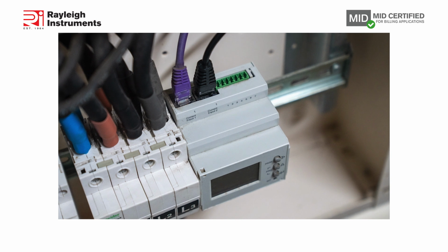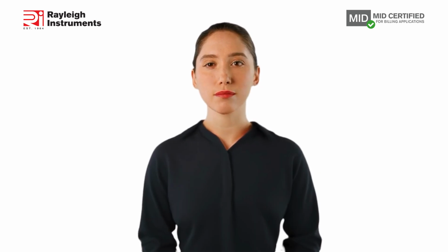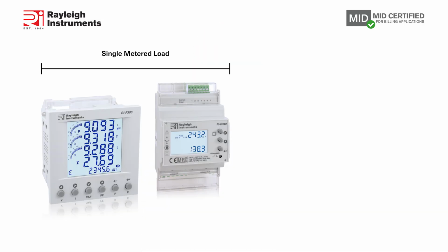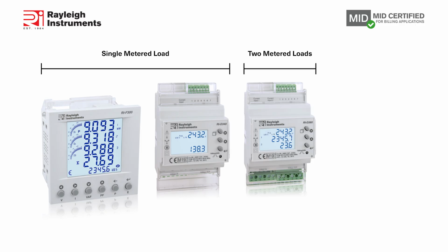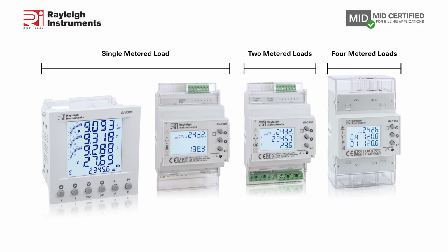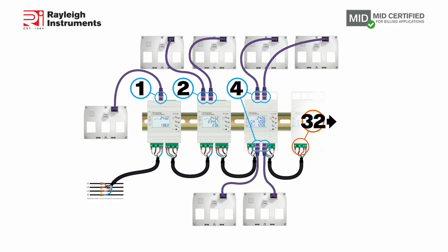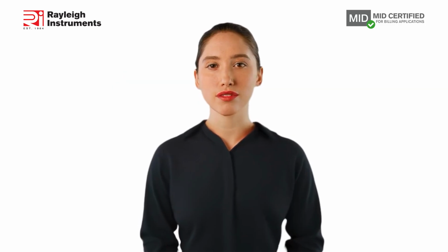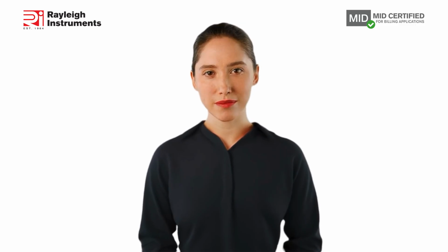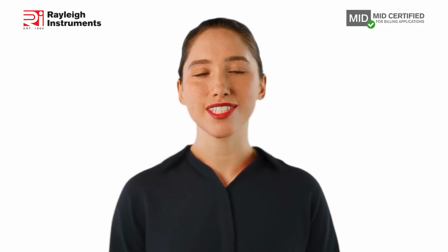To complement our Easywire CTs, we have a range of panel mounting and DIN rail mounting Easywire energy meters. These are able to monitor a single 3-phase input, 2 3-phase inputs, or 4 3-phase inputs from a single energy meter, thus enabling more CTs to be monitored by fewer meters. This can massively cut down on the amount of space required for your energy meters and it also reduces the power needed to supply them. Easywire, it's still the original and best.